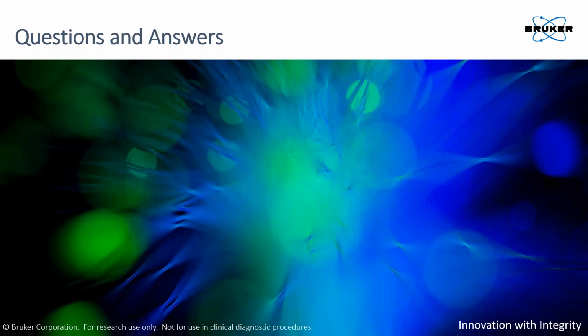Is bbCID the same as DIA with different MS1 windows? So if the question is about data independent acquisition, in a way, yes, but there are no windows, right? So all ions coming from the in-source are fragmented in broadband CID indiscriminately. So everything that comes from the source gets fragmented, and we get a full scan in high resolution from the time of flight part of the instrument.